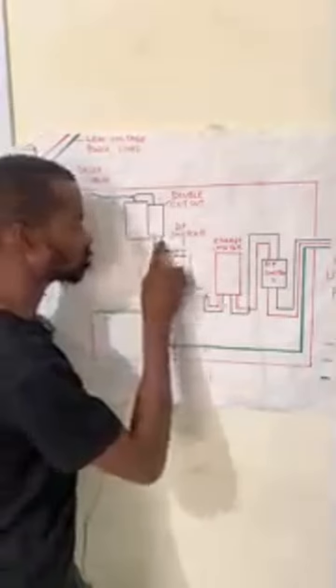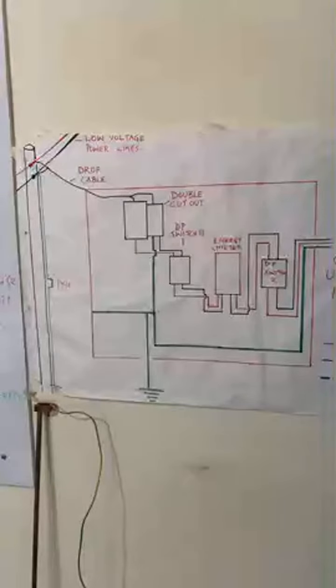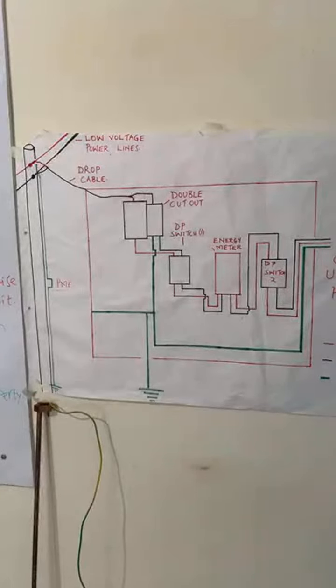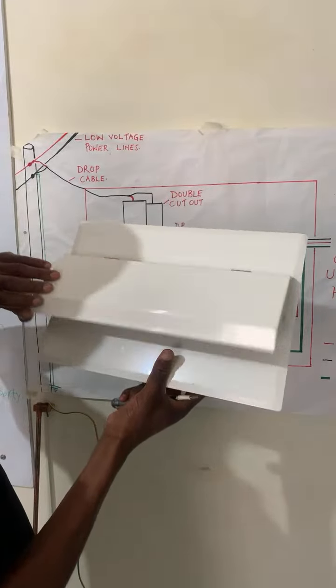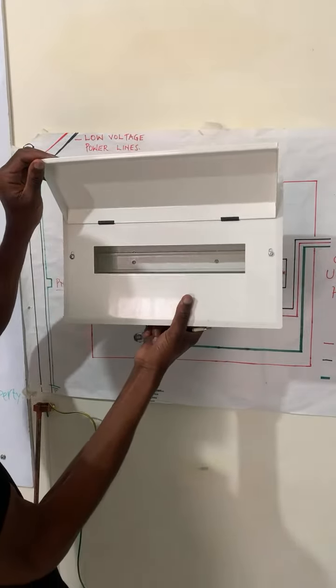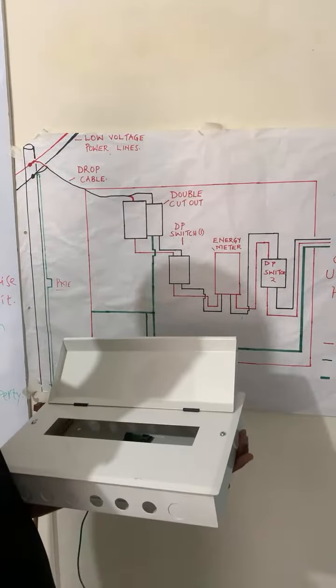So the earth and neutral connection is only done at the point where the neutral and the earth are getting into the meter, right? And then after there, when we go to the consumer unit, let me just give you a good example here. Remember, boss, we say that a consumer unit must have a lot of allowances or provisions so that if you want to have more devices connected, you definitely can. This is a 12-way consumer unit. Now let's get inside and see how the earthing is connected.